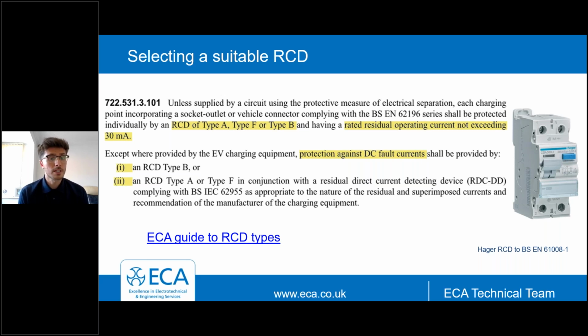actually going to need. So it tells us, except where provided by the EV charging equipment, protection against DC fault currents shall be provided by either a type B RCD or an RCD type A or type F in conjunction with a residual direct current detecting device known as an RDCDD, and this RDCDD shall comply with BS IEC 62955. And again, it alludes to recommendations of the manufacturer of the charging equipment. So I think commonly found in a lot of charging equipment is an RDCDD device, then it's required to be accompanied by a type A or type F device.